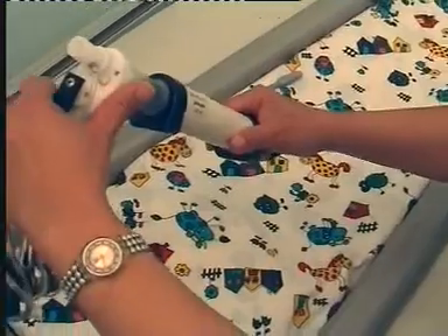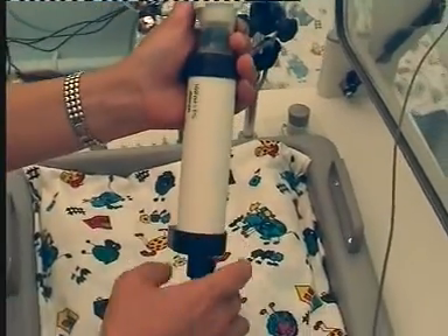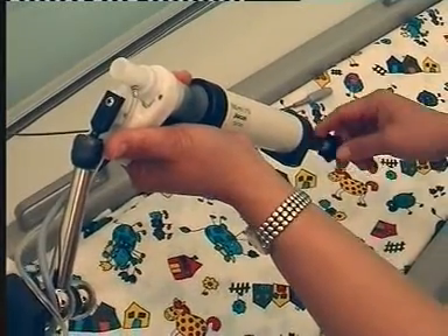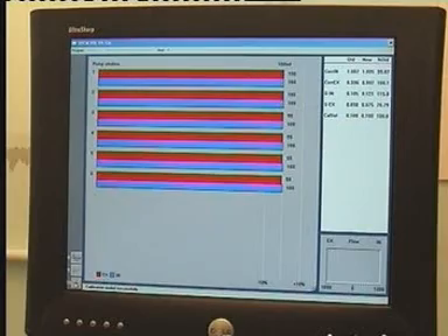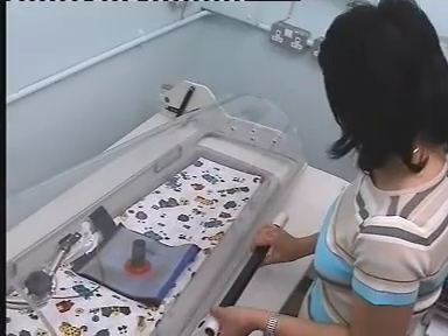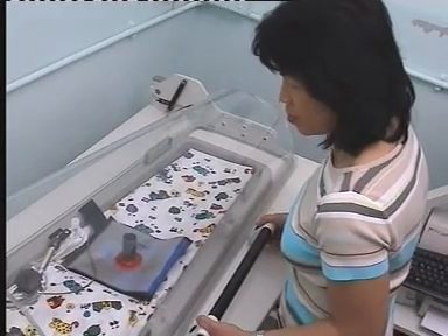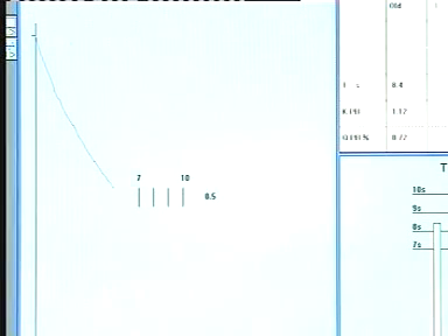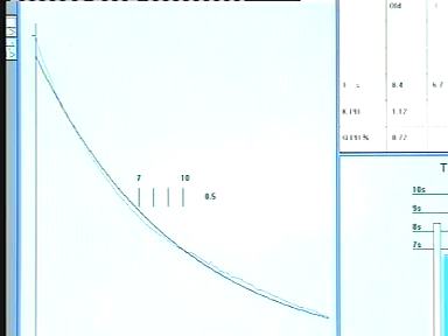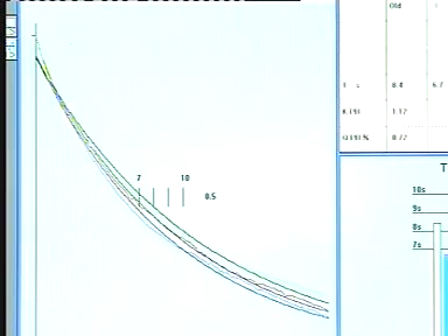The pneumotach is calibrated using a calibrated syringe to deliver a stroke volume of 100 milliliters over a range of flows. Measured volumes should be within 2% of those delivered. The plethysmograph is then closed and left for 2 to 3 minutes to reach thermal equilibrium before proceeding with calibration. The time constant indicates how long it takes for pressure changes within the box to decay and should be checked before each test. A short time constant indicates a leaky box, with loss of box pressure signal leading to unreliable results. By contrast, if the time constant is too long, box pressure will be unstable and take a long time to equilibrate. The half-life should therefore be maintained between 7 and 11 seconds.